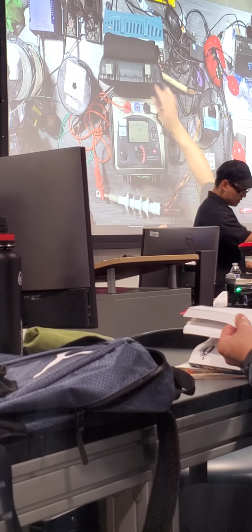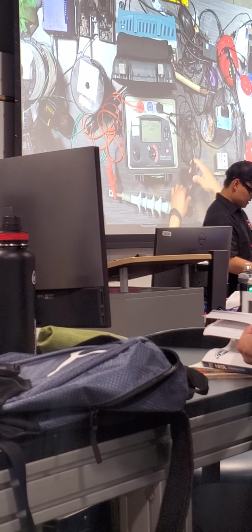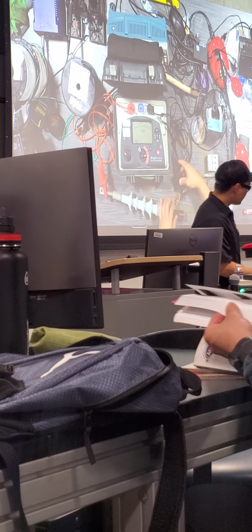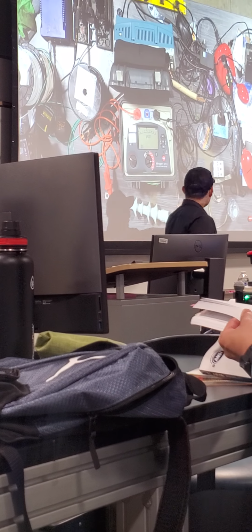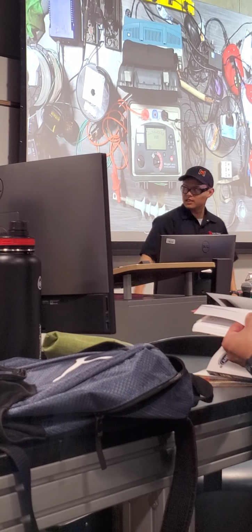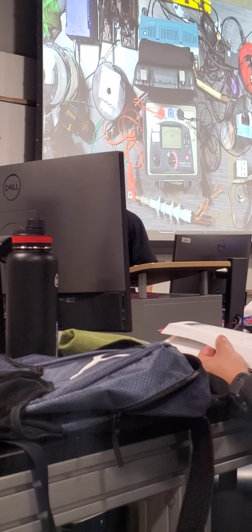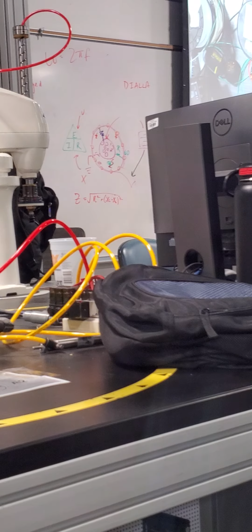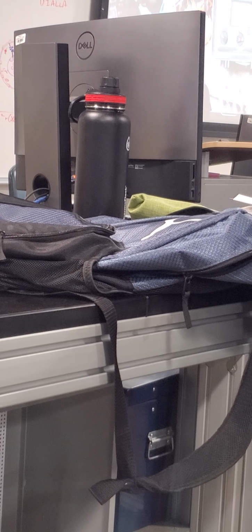All right, so now we have our return. In this case, any connection on here would effectively look at all of the wire shield connections. So if the discharge, the unintended path goes to any of these, they should catch. That's the idea. So 2.5 kV.